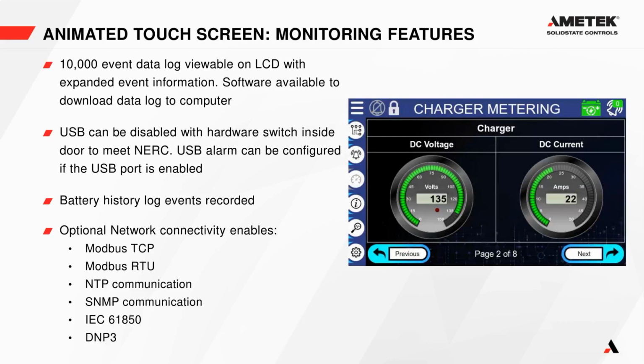The USB port can be disabled with a switch on the inside of the door to meet NERC compliance. There is also a user configurable alarm that will activate when the USB port is active. This can be turned on and off on the adjustment screen in setup. We also have the battery history log events that can be viewed on the screen or downloaded with SCI Link or the webpage. And then here's a list of our optional network connectivity features again. It's the same list I talked about previously.